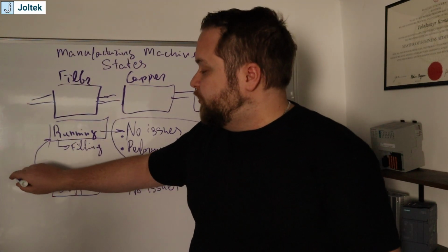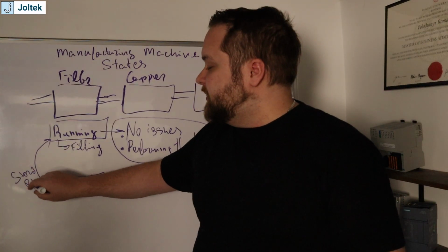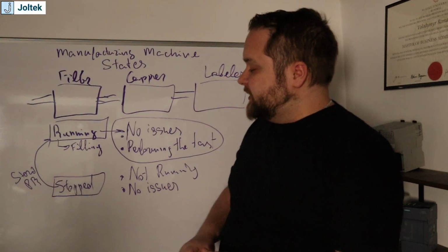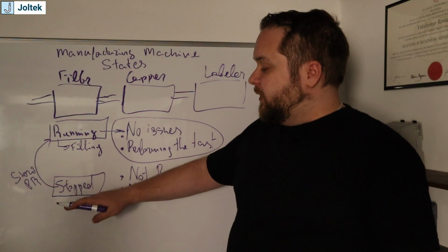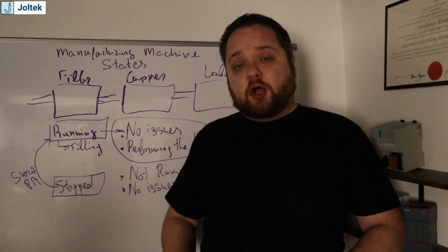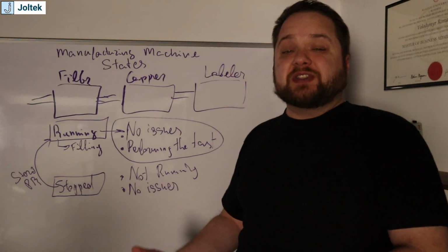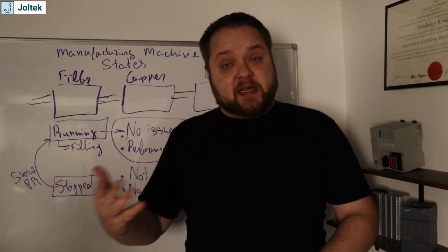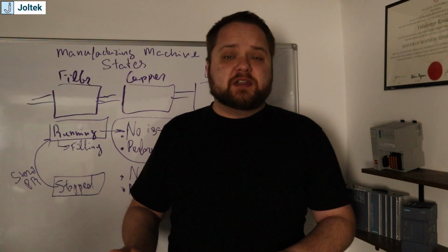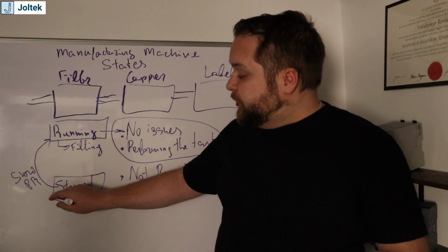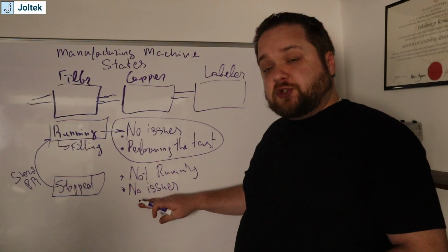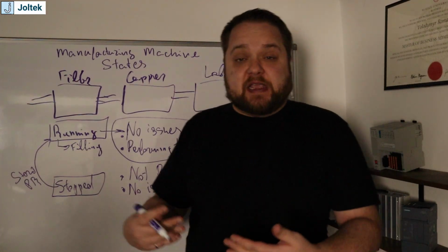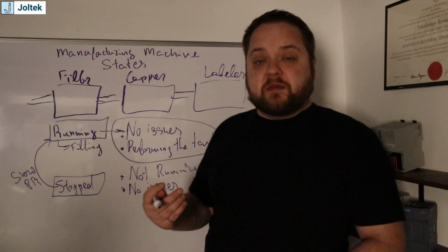So if the start push button is pressed, and of course that could be on your HMI or your SCADA system, again, we're going to spare some of the nuances, the machine is able to transition from the stopped into the running state. Now, of course, there are also different specifications and different bodies that will specify some of these states. So if you take a look at PackML as an example, PackML was originally developed for the packaging industry. It describes each one of these states, what they actually mean, and some of the possible transitions between the states.